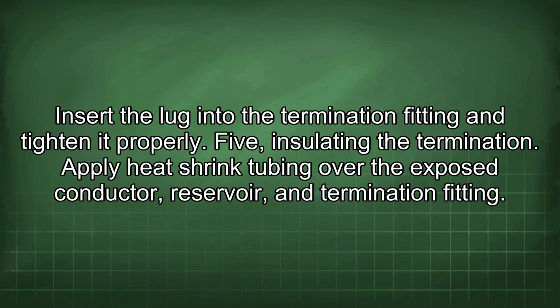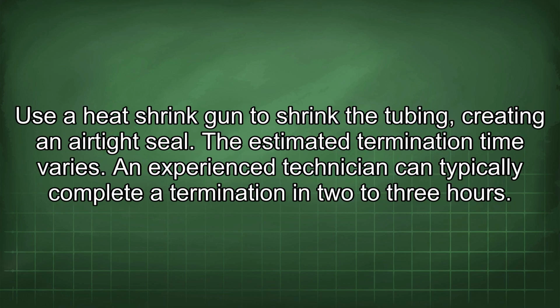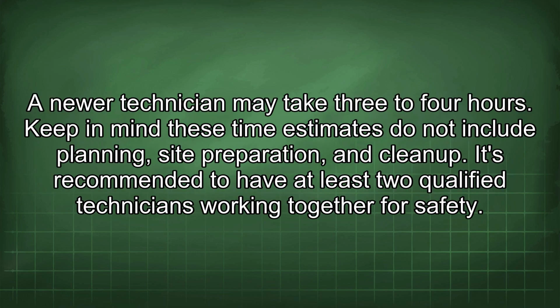5. Insulating the termination. Apply heat shrink tubing over the exposed conductor, reservoir, and termination fitting. Use a heat shrink gun to shrink the tubing, creating an airtight seal. The estimated termination time varies. An experienced technician can typically complete a termination in 2 to 3 hours. A newer technician may take 3 to 4 hours.